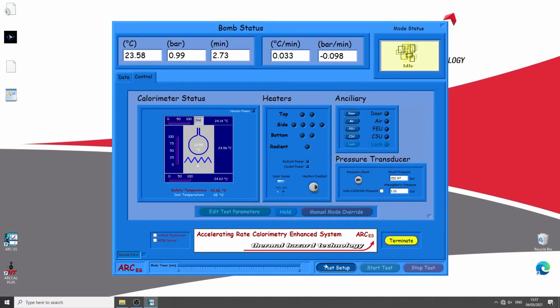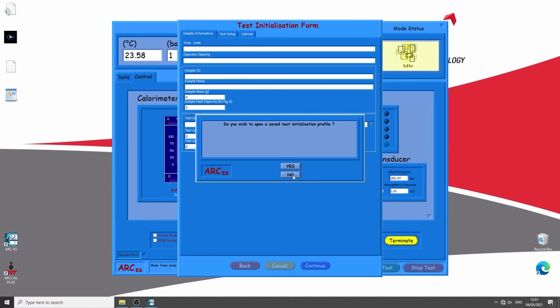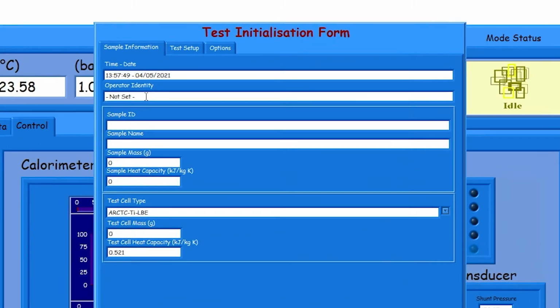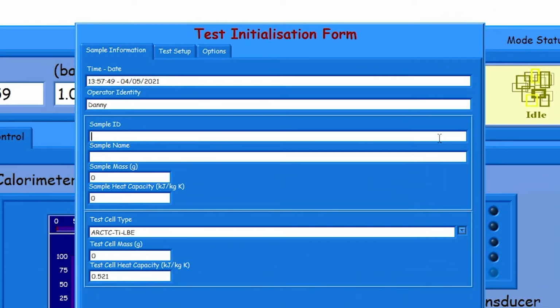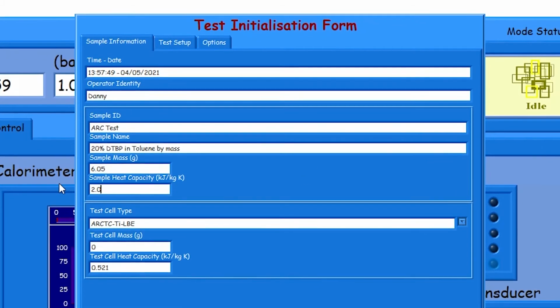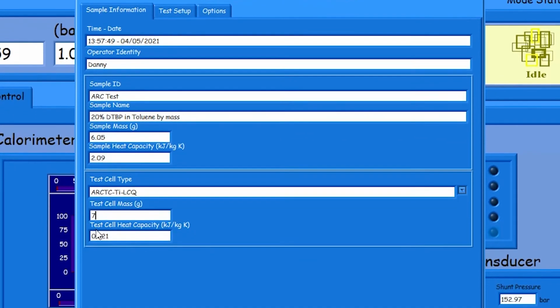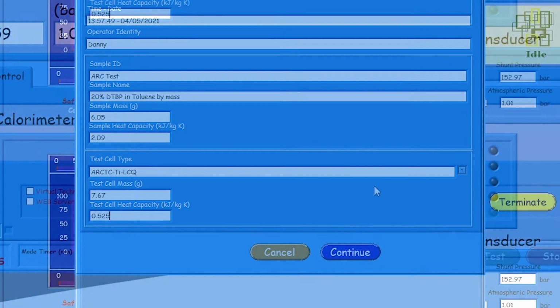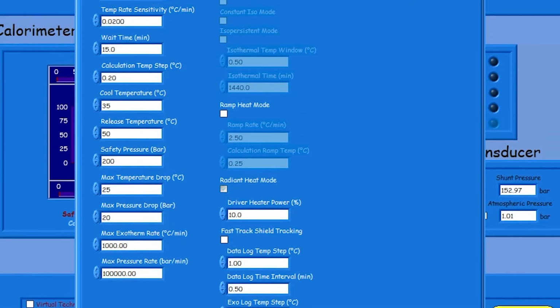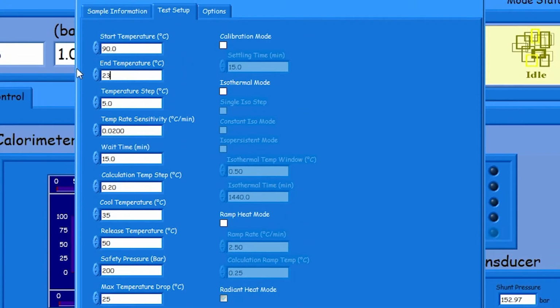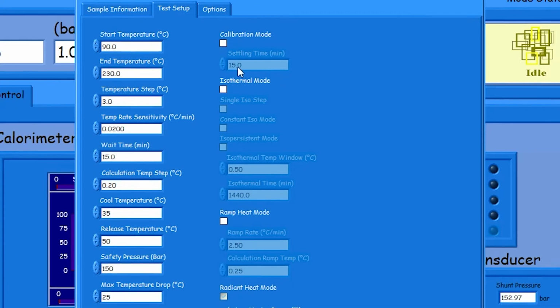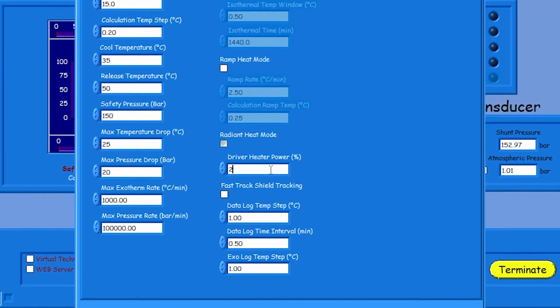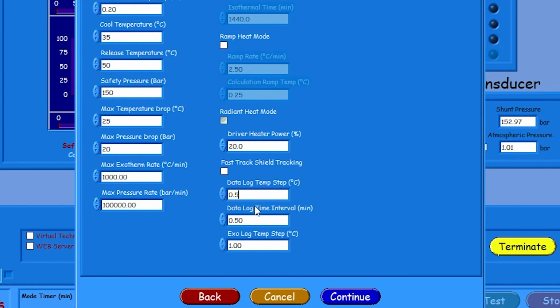Press the Test Setup button to configure a new test. An existing test profile or a new blank profile can be used. In the Sample Information tab, enter the details of the sample which is being tested, including the mass and heat capacity of both the sample and the test cell. Continue to the Test Setup tab. Enter the required test conditions in the text boxes. Select special operating modes such as isothermal mode using the tick boxes on the right-hand side.